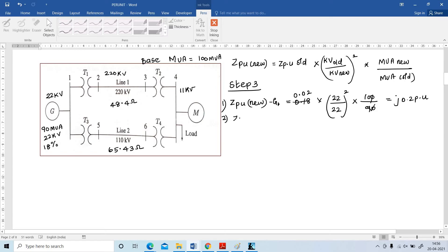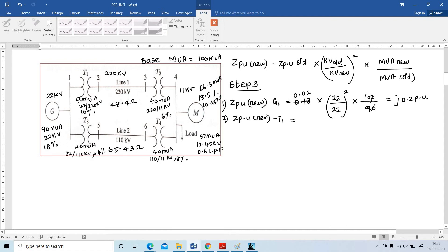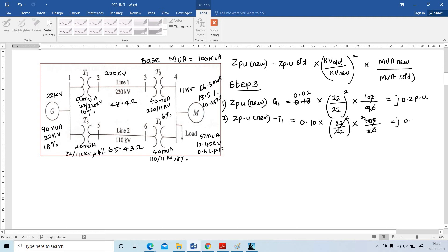Next, find ZPU for transformer T1. ZPU(new) = 0.10 × (22/22)² × (100/50) = j 0.2 per unit.